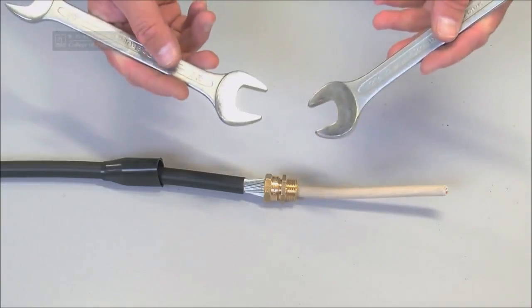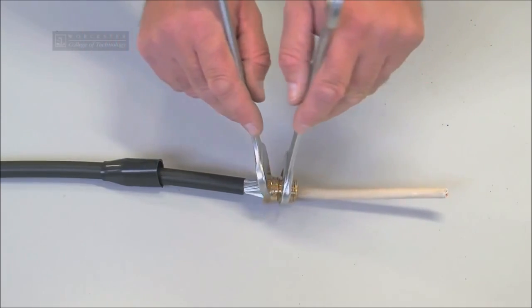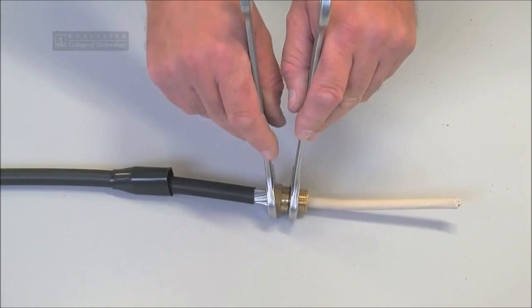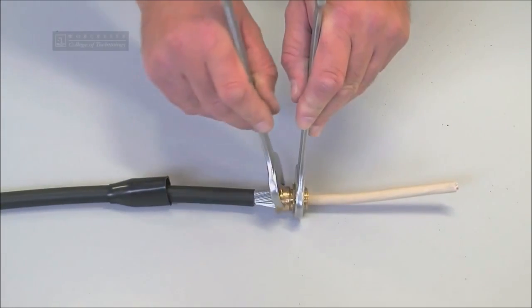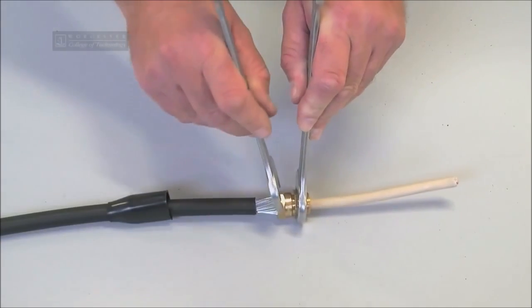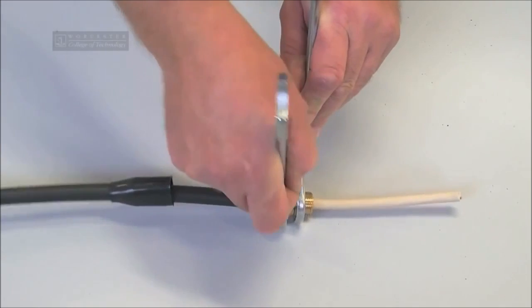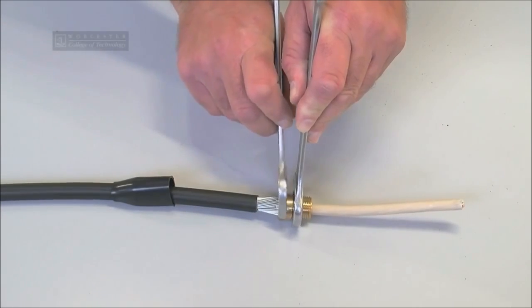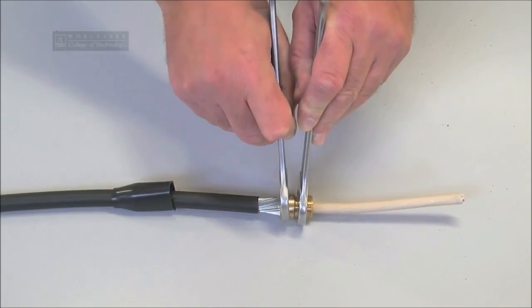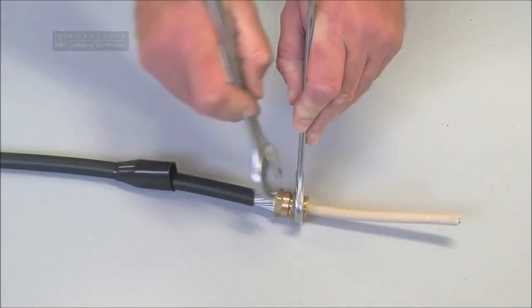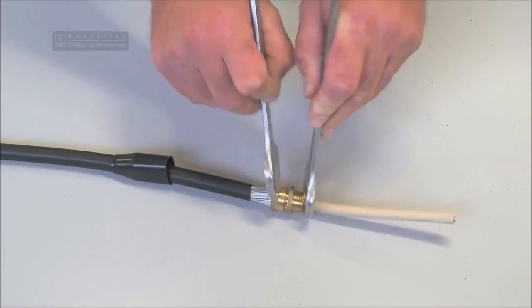We now use 2 22mm spanners to tighten up the gland. And we ensure that these are as tight as we can possibly get them, as the metal braiding is sometimes used as the CPC in the installation.